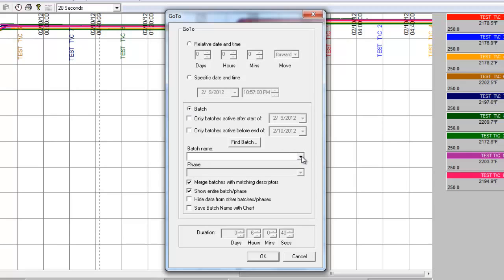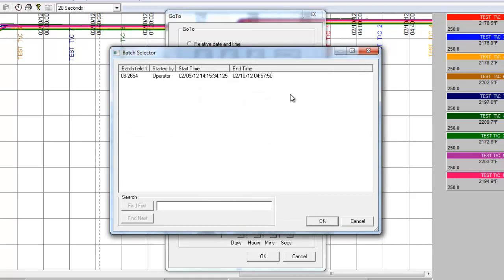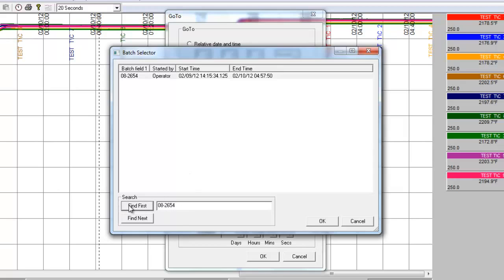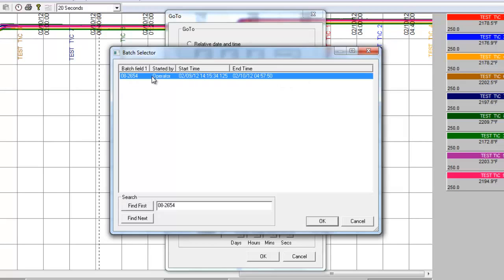For this example, clicking on the drop down window underneath batch name will suffice because we only have one batch. Let's say for example we have multiple batches, maybe somewhere around 25 to 30 different batches. If we click on the find batch window, they'll all be listed here. What's a nice feature is that you can actually do a search for a specific batch field. It does not matter which field you're looking at, you can search for anything. For this particular example, they only utilized one batch field. You can have up to 10 batch fields in our 6000 series recorders. So once I put in what field I want to look for, I do a find first. And obviously you can see by the light blue color that the first one is selected. When I select that, I click on OK and that batch is selected. Now that I've got that batch selected, I can go ahead and click on the OK button.